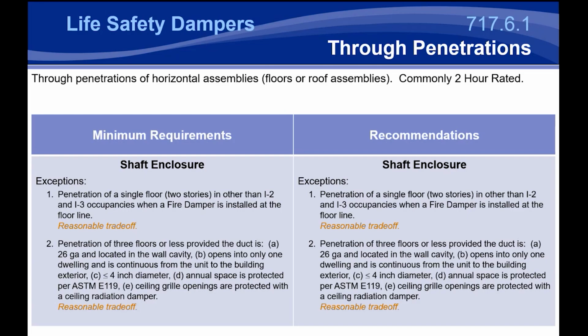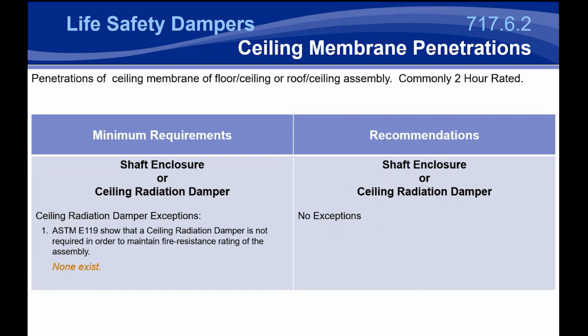And when you're protecting that ceiling membrane, there's very little risk of smoke and fire circulating through that building without the need for a shaft to protect that. Now, for a ceiling membrane penetration, for the most part, you're using a ceiling damper, and you're going to have to use something like that. Now, if there is no ceiling damper, you can put in a shaft enclosure, but that's going to get very costly. It may be the only option for a through penetration, but you can certainly use a shaft if you want to for that type of application, though it is quite rare. Most of the time, you're dealing with a ceiling radiation damper, or you're dealing with some other type of assembly.